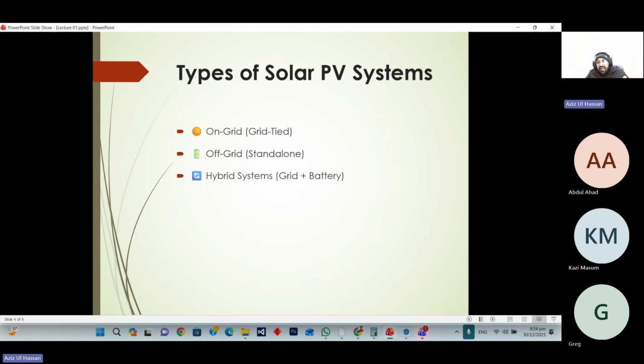Now, what is the difference between these three systems? On grid, basically, they have just two sources. One is the grid, and the other one is the solar system. They will combine those two sources of energy at one level, on one inverter. That inverter is called the grid tied inverter, and when the grid is shut down, your solar system will automatically stop working. They will not provide power to the home appliances.